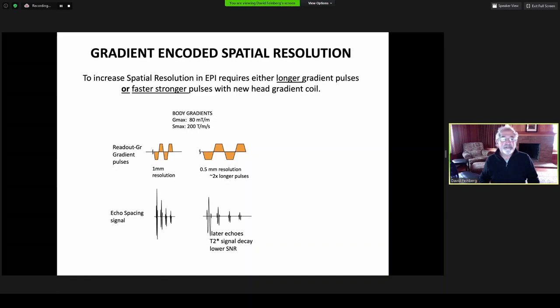Gradient encoding is a very critical part of this higher resolution. I'll show you a basic echo planar readout sequence where the brown boxes are the time integral of the pulses, and the area of those boxes or pulses is proportional to the resolution. To go to higher resolution, 0.5 millimeter, we need to double the length of the pulse using the maximum gradient already with standard body gradients. The higher resolution lengthens the echo time, leading to more T2-star decay and lower signal-to-noise in the image.